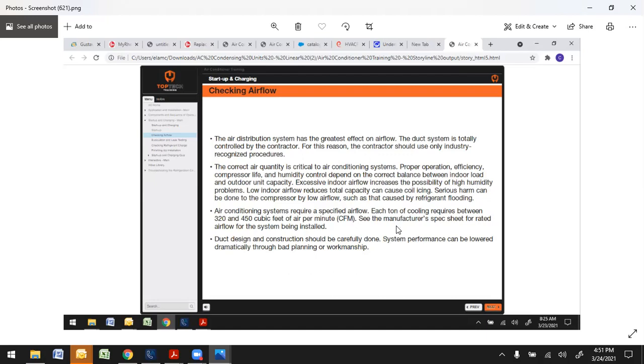If you have excessive indoor airflow, it increases the possibility of high humidity problems. We see that quite often. Low indoor airflow reduces the total capacity and can cause your coil to freeze up. Serious harm can be done to the compressor by extremely low airflow, such as that caused by refrigerant flooding. So it's important to understand what size system you have, how much airflow is needed, and whether your duct system can handle the airflow. If you do have humidity issues, you can usually slow the fan down slightly, as long as you're within a certain range, and that's going to give you better dehumidification.